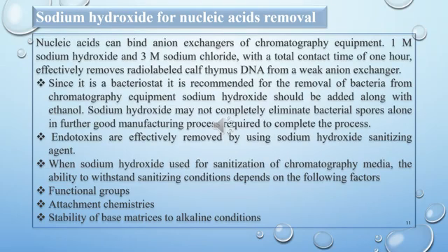Dear students, till now we have discussed how sodium hydroxide is being used for the removal of proteins. Now we are going to discuss how we can remove nucleic acids by the use of sodium hydroxide. Nucleic acids can bind anion exchangers of chromatography equipment. 1 molar sodium hydroxide and 3 molar sodium chloride with a total contact time of 1 hour effectively removes radio-labeled calf thymus DNA from a weak anion exchanger.